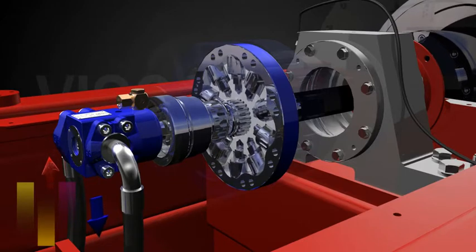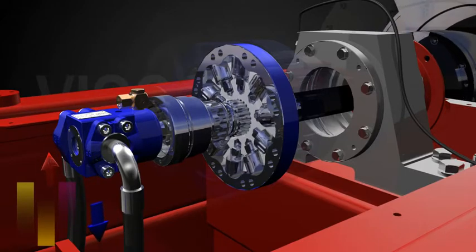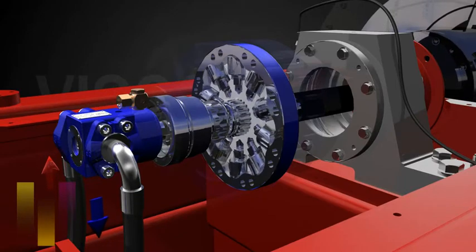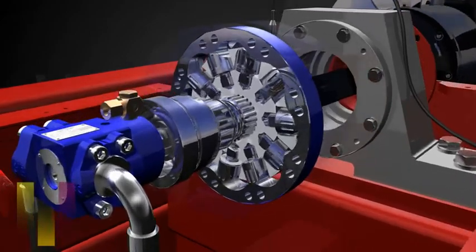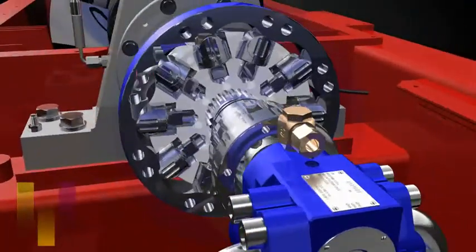The solid loading, respectively the conveyor torque, is directly proportional to the hydraulic system pressure. This allows simple and direct speed control, which enables immediate response to any process changes.